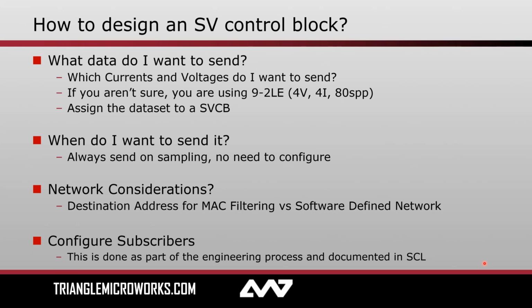Network considerations become more important for sample values, even more so than they were for GOOSE. We might want to take advantage of MAC address filtering or some sort of software-defined network, using intelligent switches to decide what data goes where. However, if you are using testing devices like DTM or Test Suite Pro, you might need a port where all this data is aggregated so that you can use these test sets without having to move them around the substation to different points. And then finally, configuring subscribers. Pretty similar to how we did it with GOOSE, you're ultimately going to do this in a system configuration tool and decide which devices you want to receive this data, who needs it in order to perform their protection, automation, or control functionality.